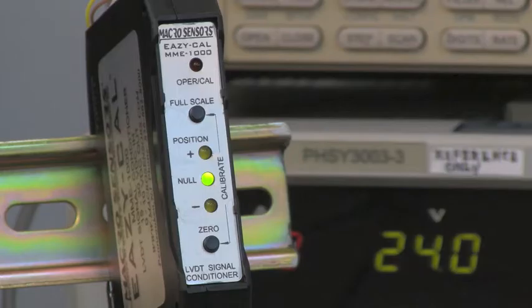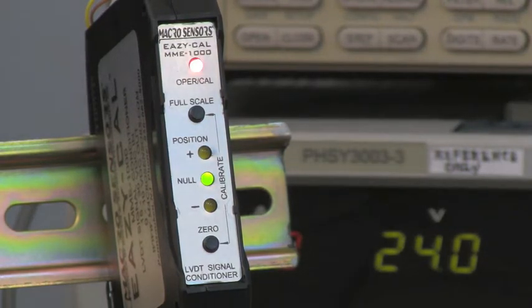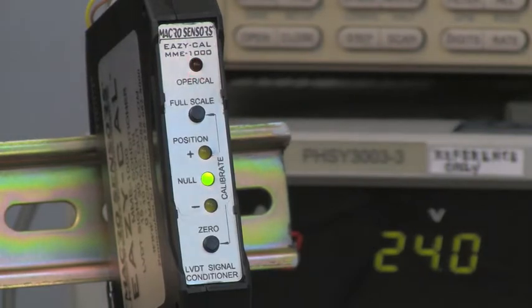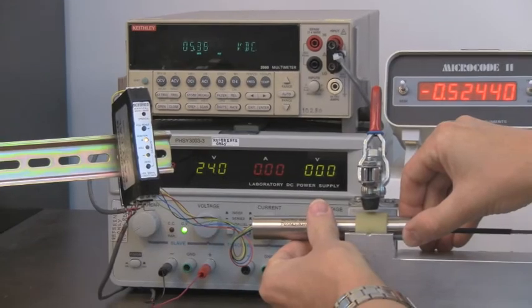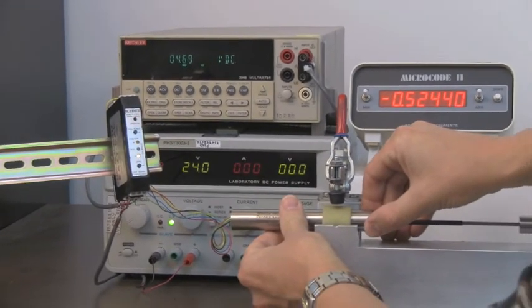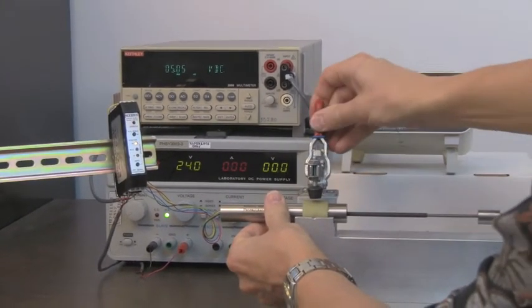When perfectly centered, the null LED indicator lamp will be steadily illuminated, meaning that the LVDT is at the center of its total stroke or at null. We then position the coil in the test fixture as closely as possible to null and lock the coil in place.